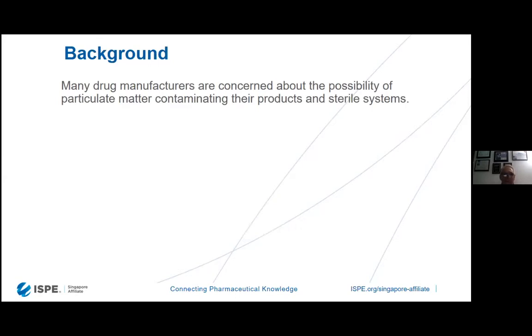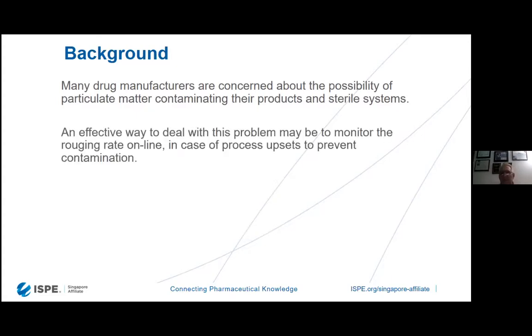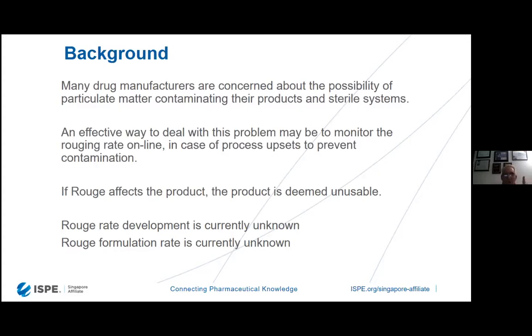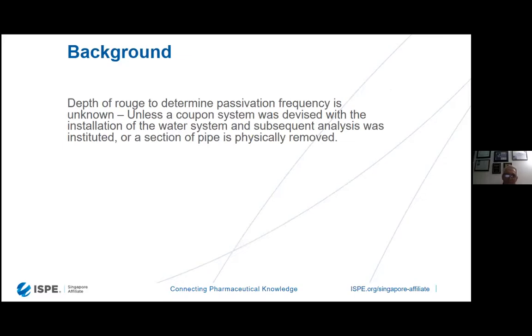Many drug manufacturers are concerned about the possibility of particulate matter contaminating their products in sterile systems. An effective way to deal with this problem, though, may be to monitor the rouge rate online, and in case of process upsets, to prevent the contamination from causing a process upset, which is probably more effective. If rouge does affect the product, though, the product is deemed unusable. Currently, though, in most sites, rouge rate development is unknown, and the formation rate is unknown because there's no way to monitor it.